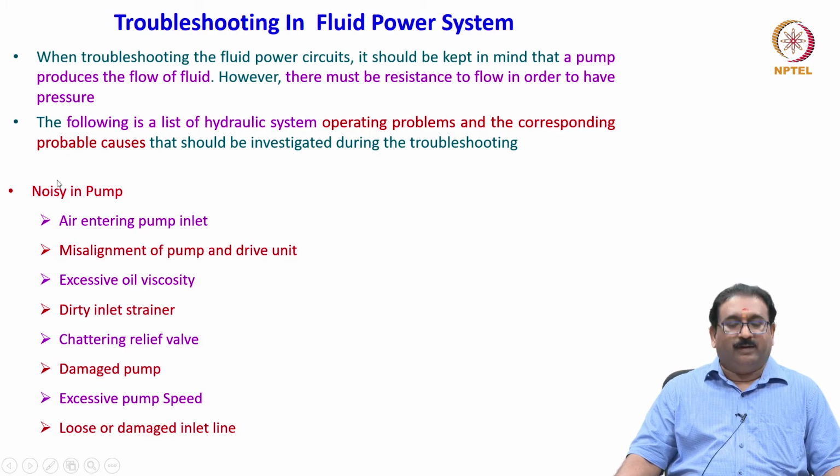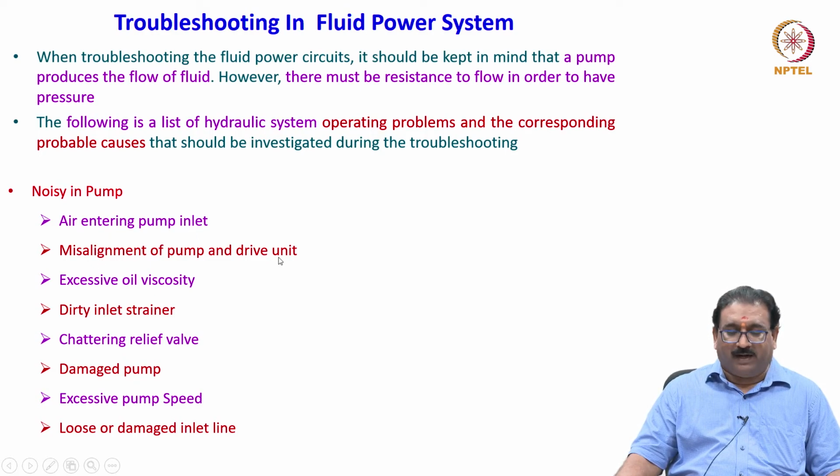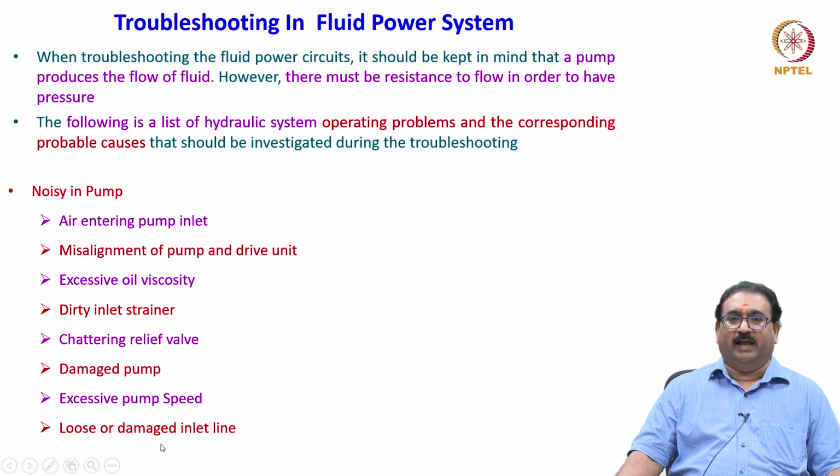Noise in a pump may be due to air entering the pump inlet, misalignment of pump and drive unit, excessive oil viscosity, dirty inlet strainer, chattering relief valve, damaged pump, excessive pump speed, or a loose or damaged inlet line.